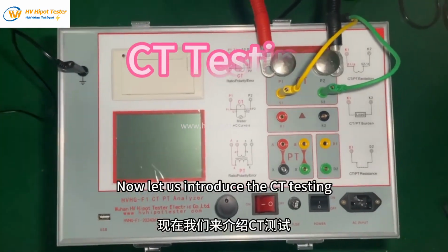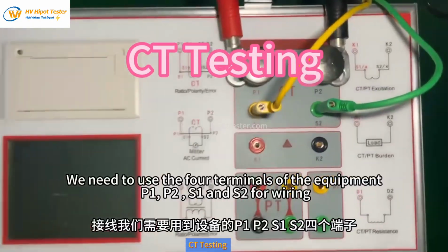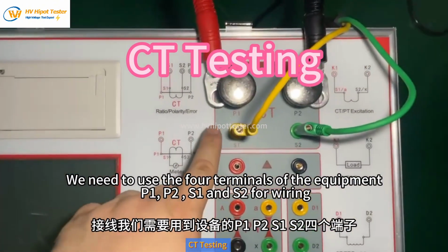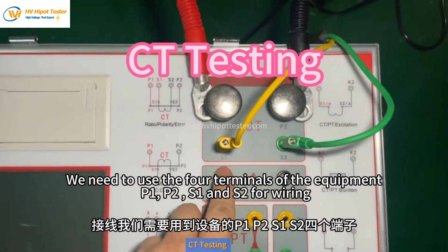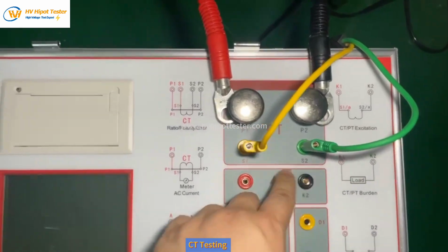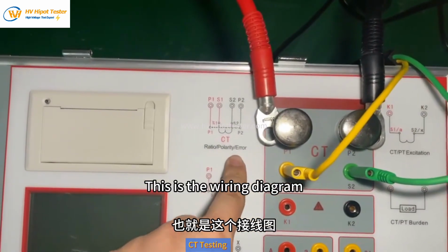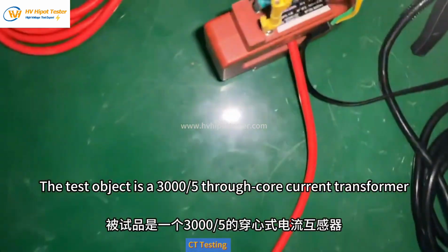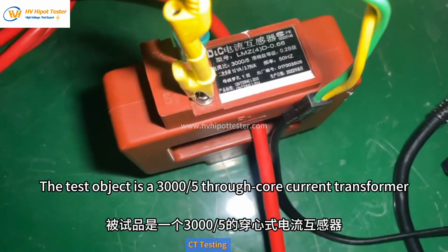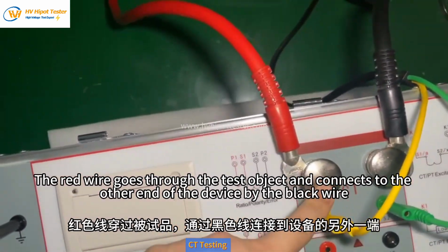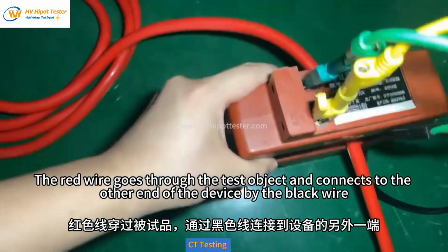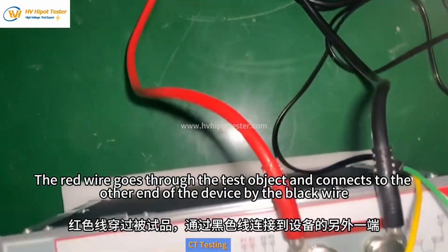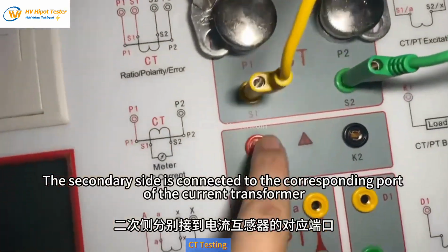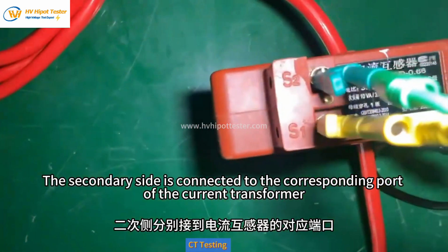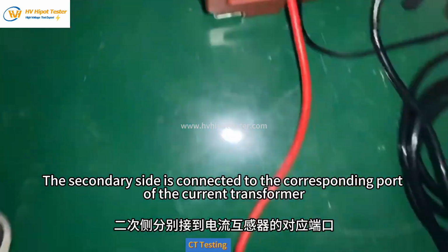Now let us introduce the CT testing. We need to use the 4 terminals of the equipment P1, P2, S1 and S2 for wiring. This is the wiring diagram. The test object is a 300/5 through-core current transformer. The red wire goes through the test object and connects to the other end of the device by the black wire. The secondary side is connected to the corresponding port of the current transformer.